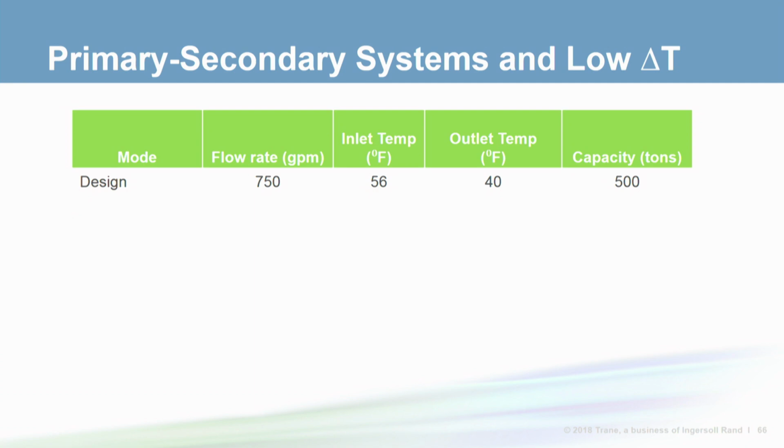In addition, some of the air handler controllers aren't working properly. The result is that the return water temperature from the system is only 50 degrees, even though the flow rate is 1,000 GPM.